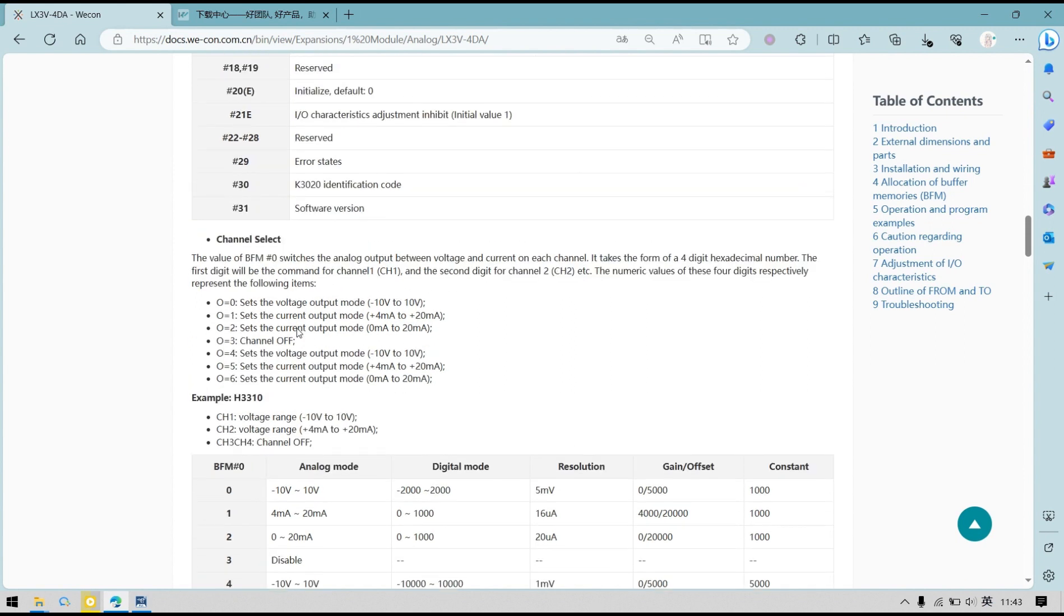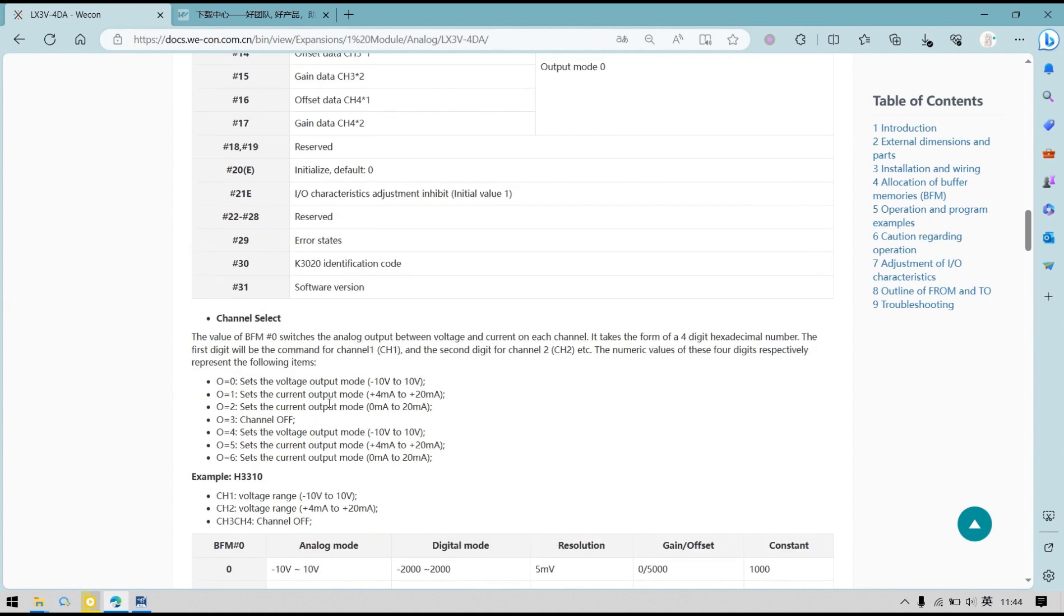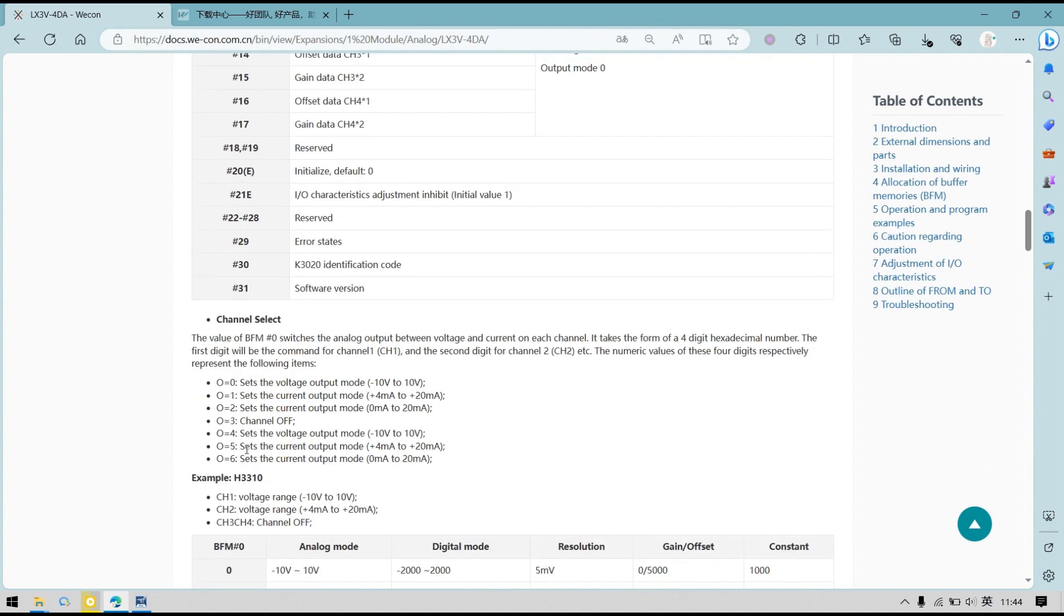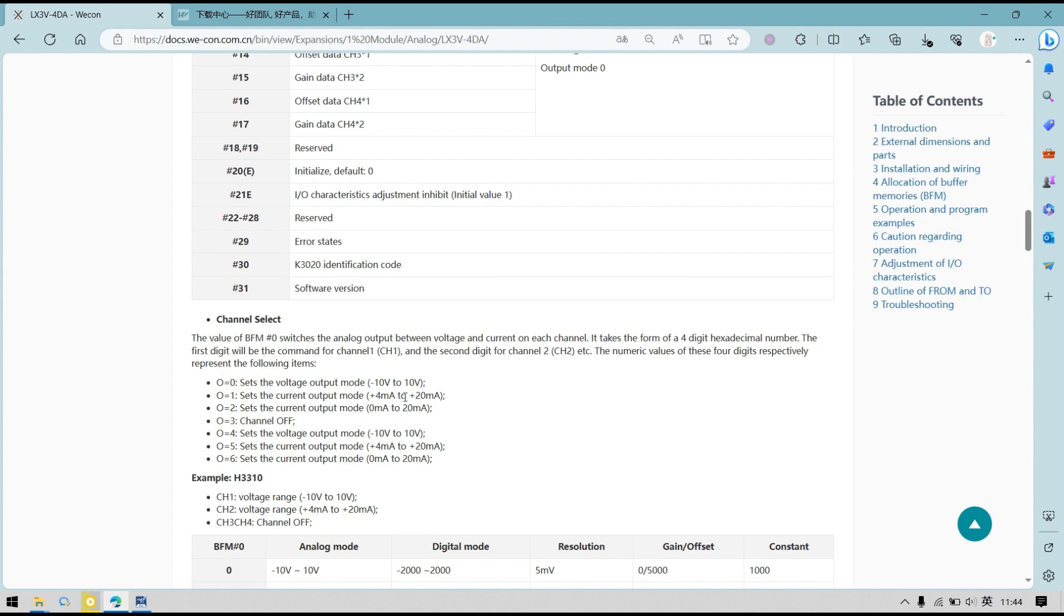For example, if we write H3310 to BFM0, this value refers to channel 1, and this refers to channel 2. Different values mean different ranges. In channel 1, it's minus 10 to 10V output, and for channel 2, it is 4mA to 20mA output.